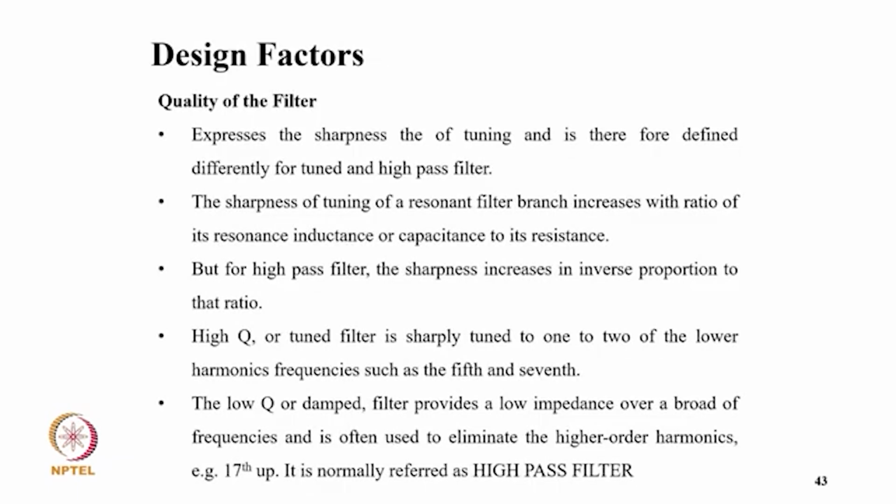So now coming to quality of the filter, it expresses the sharpness of the tuning and is therefore defined differently for tuned and high pass filters. The sharpness of tuning of a resonant branch increases with the ratio of resonance inductance or capacitance to its resistance, but for a high pass filter the sharpness increases in inverse proportion to that ratio.